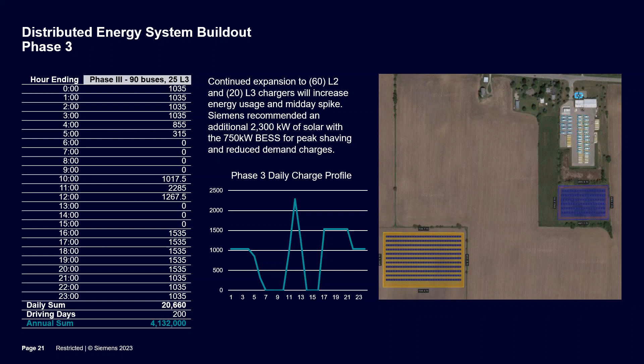Continued expansion to 90 buses with 60 level 2 chargers and 20 level 3 chargers. We recommended a 2,300 kilowatt solar array with a 750 kilowatt battery energy storage system for peak shaving and reduced demand charges. This is how we designed the enhanced energy supply for their growing power demand for those 90 electric buses.